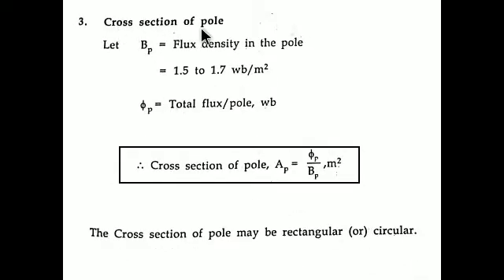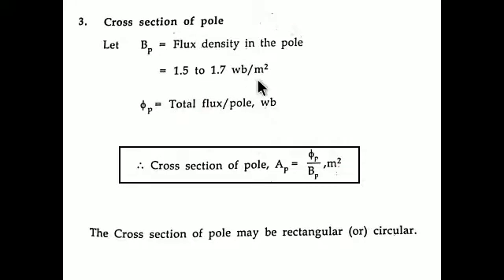The third design step is the cross-section area of the pole, denoted Ap. It is found by dividing the total flux per pole φp by the flux density in the pole Bp: Ap = φp / Bp. The flux density Bp is an assumed value lying between 1.5 to 1.7 Weber per meter square. During a problem you must assume a value within this range.